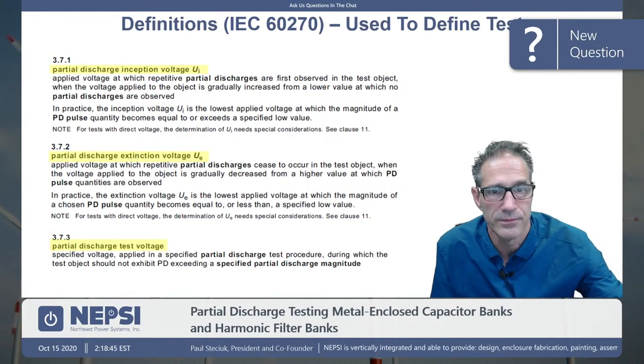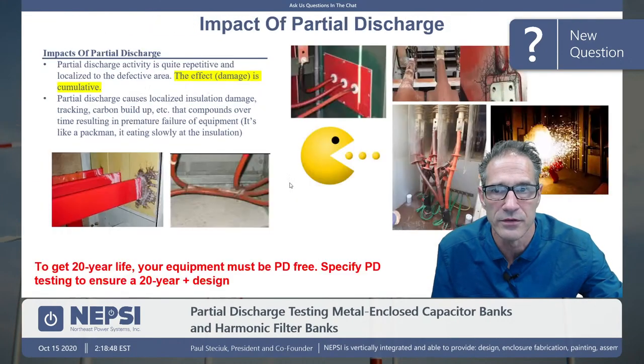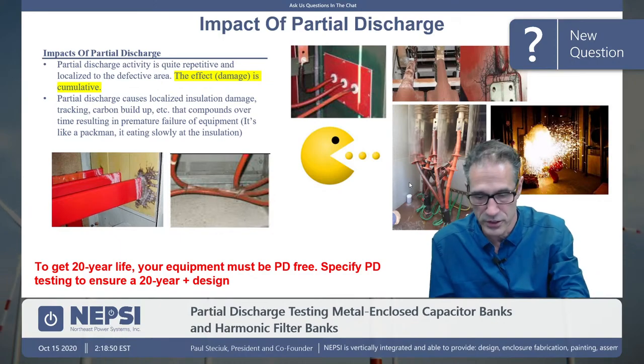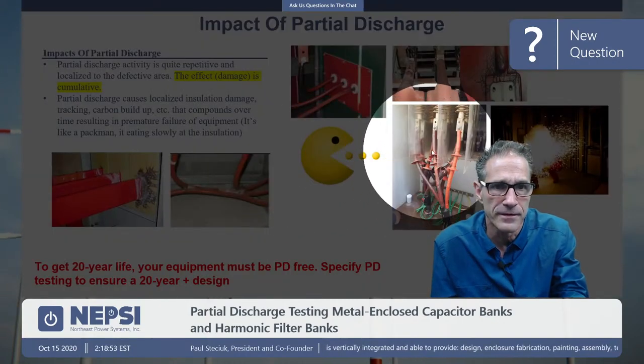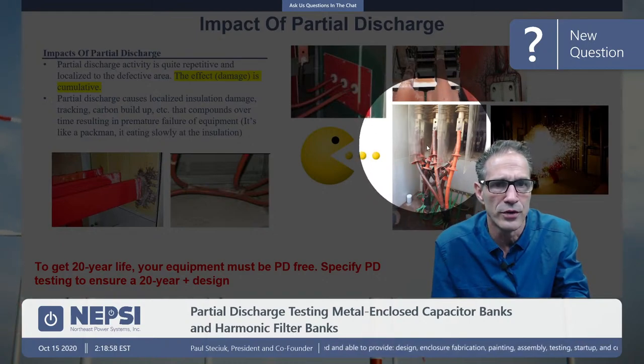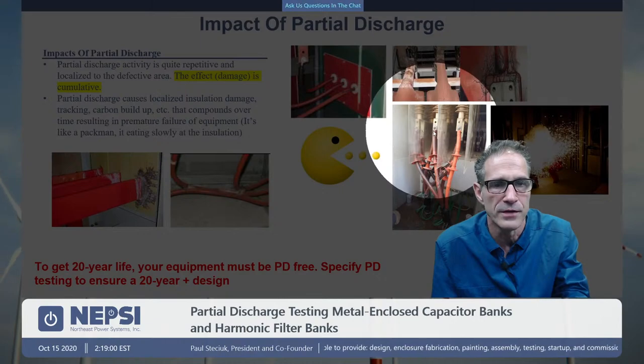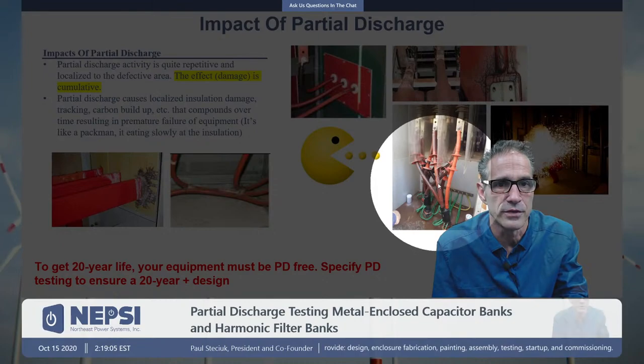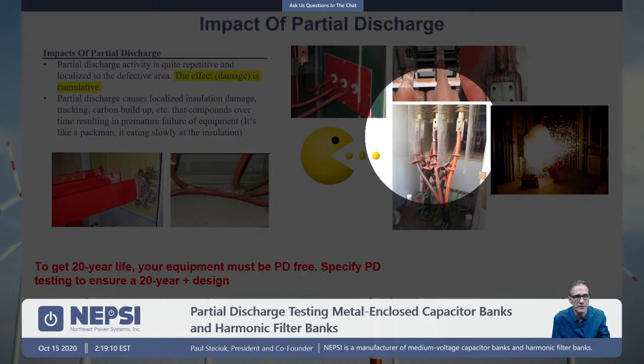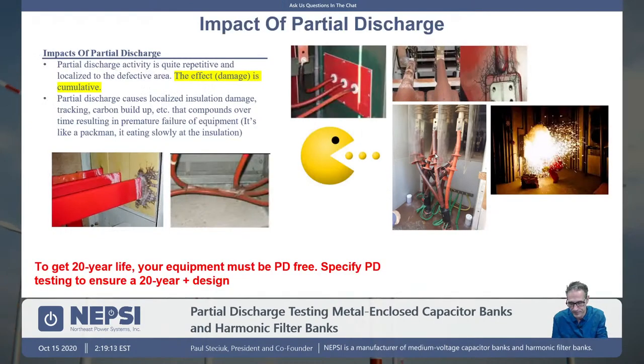Maybe I'll just tab back real quick and go back to that medium voltage termination. Okay, so we're talking about these devices here, their terminations. And I think you can see my mouse pointer. So you got high voltage here, and you strip the ground shield off the cable, I think back to about this point here. And so this insulation around the cable, it's not insulation, but it's a sleeve that goes around the outside of the cable. It's designed to grade the electric field, okay?